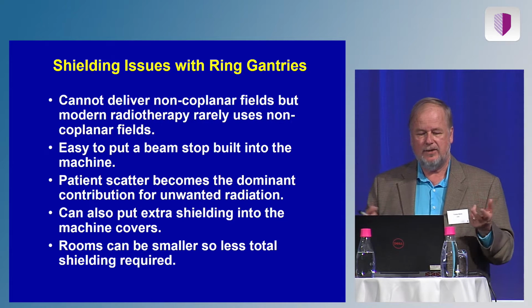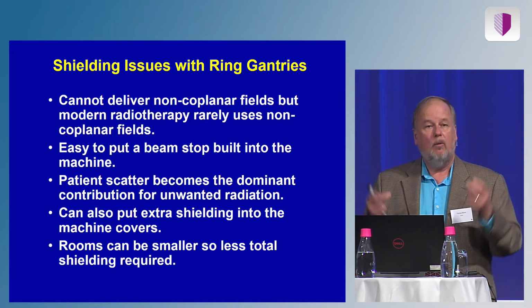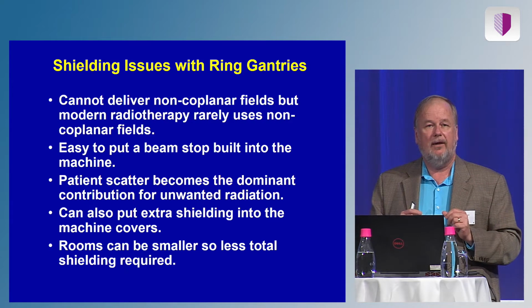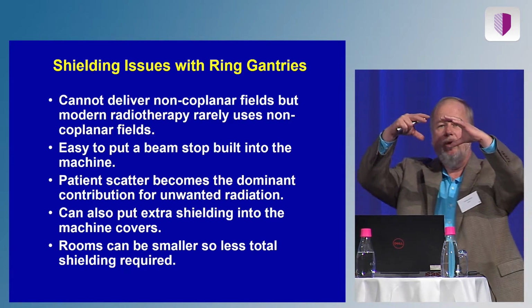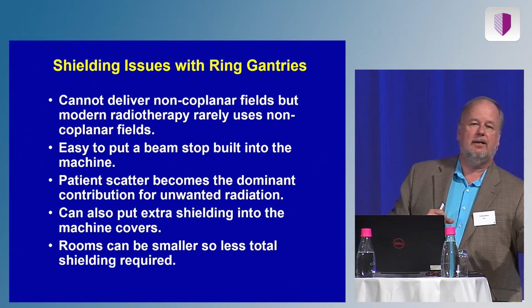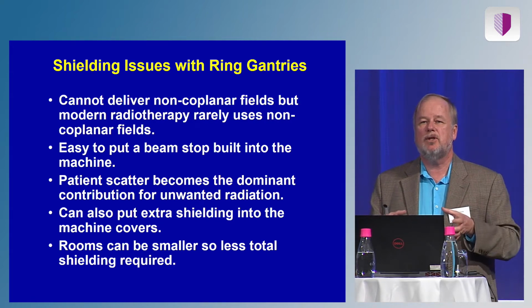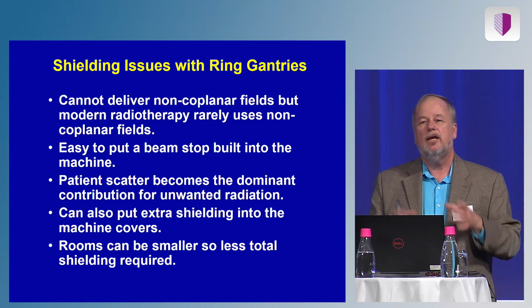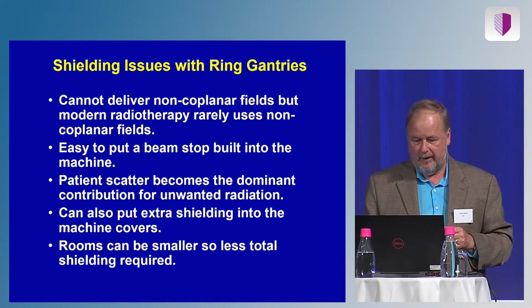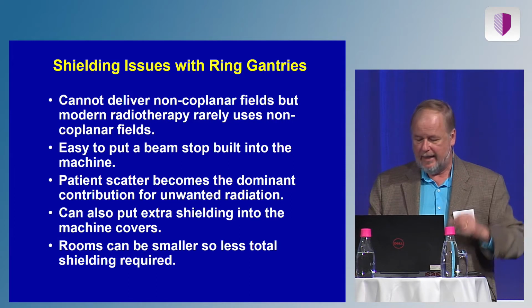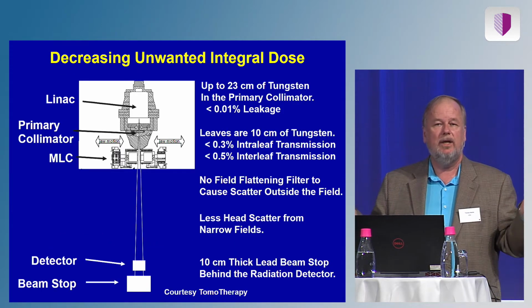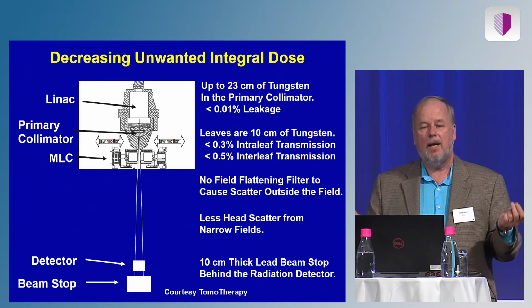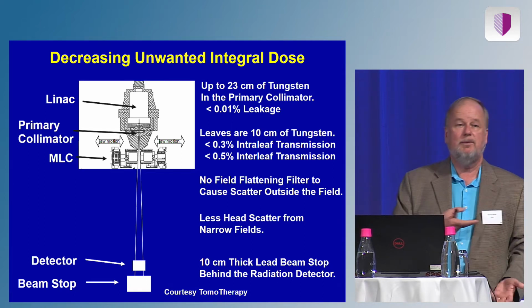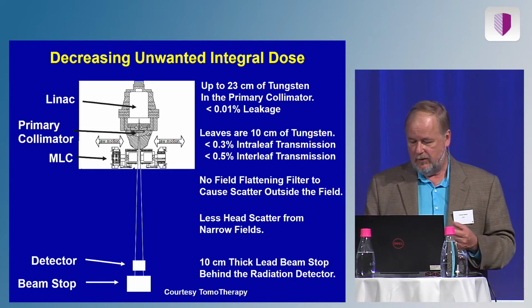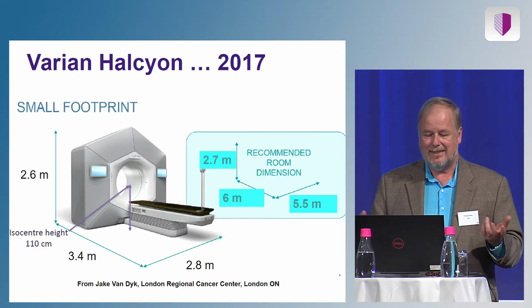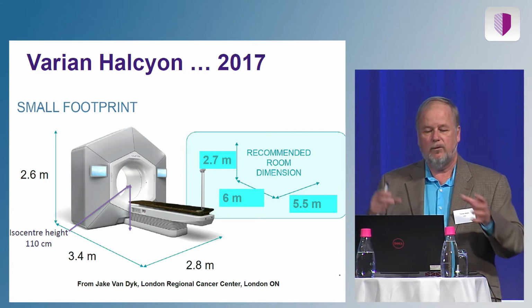I won't go into the details here, but one of the other reasons important for radiation protection is that when you don't have the ability to kick the couch, it's much easier to put a beam stop in so that the primary beam is shielded. You don't have to worry about the shielding on the rooms, and you can also put in extra shielding in the covers. Basically, we did this with tomotherapy. We put in a lot more primary collimation, a lot thicker leaves, and a beam stop into the beam so that it was stopped. And Halcyon from Varian is essentially doing the same thing. And the footprint of the room is very, very small.